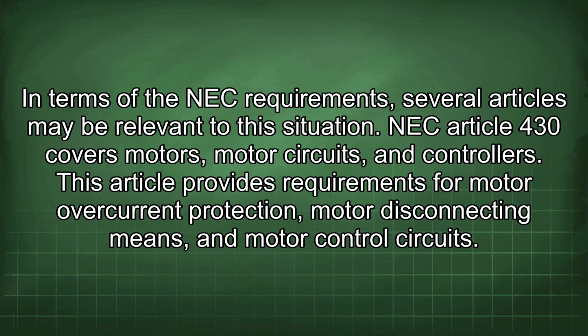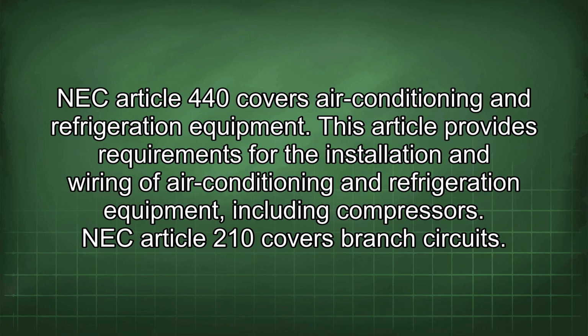In terms of the NEC requirements, several articles may be relevant to this situation. NEC Article 430 covers motors, motor circuits, and controllers. This article provides requirements for motor overcurrent protection, motor disconnecting means, and motor control circuits. NEC Article 440 covers air conditioning and refrigeration equipment. This article provides requirements for the installation and wiring of air conditioning and refrigeration equipment, including compressors.